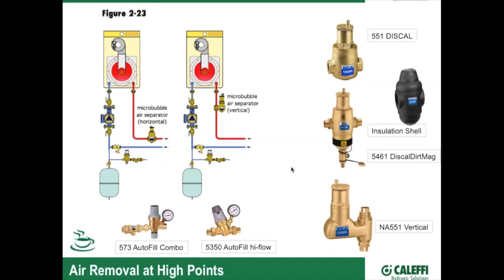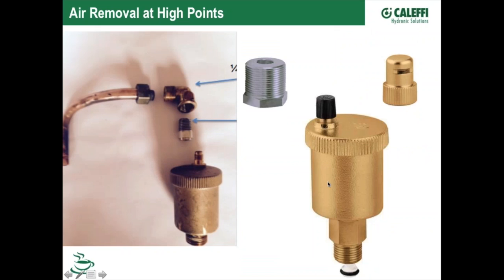This here is another vent that we offer, a little float vent, and this vent is intended to be used at high points in the system. You wouldn't just screw this into a T right next to the outlet of the boiler and expect it to do a good job of air removal, because there's really nothing to coax the air up into the chamber where it can be removed.